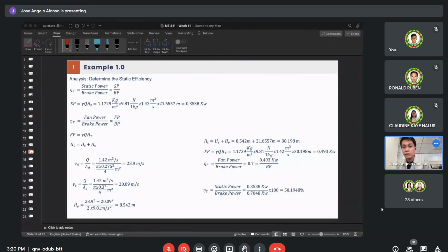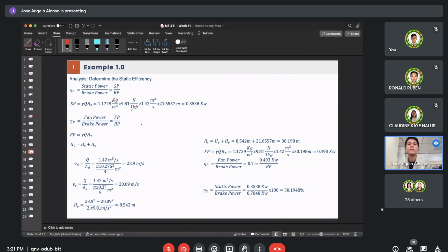Kailangan natin ma-determine muna si static power. Static power is a product of the density ng air, 1.1729 kilogram per cubic meter, acceleration due to gravity, which is 9.81 meter per second squared. Ginawa ko lang siyang conversion factor para ma-cancel. Multiply by the fan capacity of 1.42 cubic meters per second, and multiply to the static head of air, which is 21.6557 meters. So it will give us a static power of 0.3538 kilowatts.